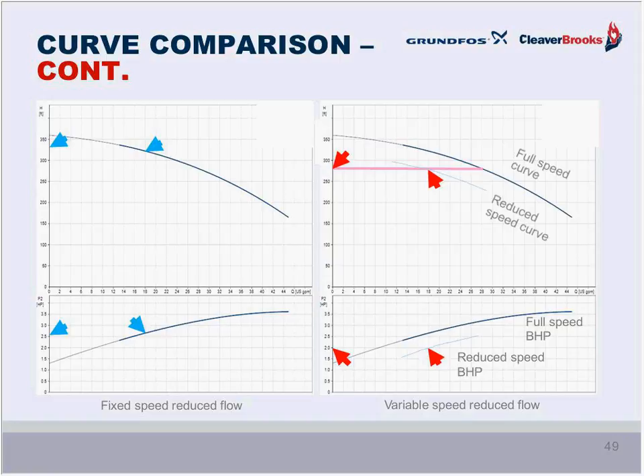The variable speed pump on the right, using this pressure control, and we're using the red arrows, we don't operate on the black curve line. We operate on that magenta line. So as the flow is reduced to 18 gallons a minute, perhaps, the head is reduced. Instead of being 325 feet, it's only 272 feet. And that gives us a load down at that point of only about 1.9 brake horsepower, significantly less than the 2.4 with the other method.